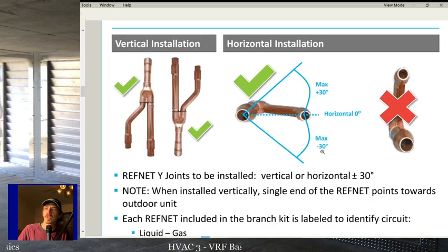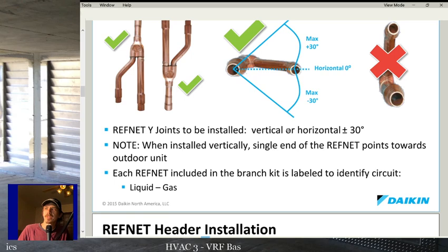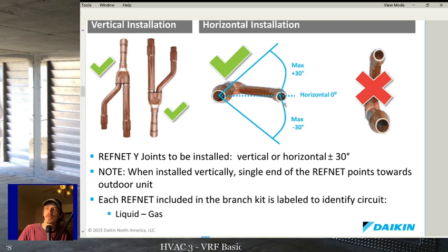and that is a bad thing. And pretty much all of them will tell you it can be installed vertical or horizontal plus or minus 30 degrees, so they say it can be off by 30 degrees one way or the other, but anytime you take the actual class, they'll tell you no, it pretty much has to be level. Don't play with having it 15 or 20 degrees off. Make it level. So that's one real good lesson from VRF as we talk about all this. Learn to think about refrigerant piping as if there's liquid and gas in it, and when you're running it, think about where the liquid would go and where the gas would go.